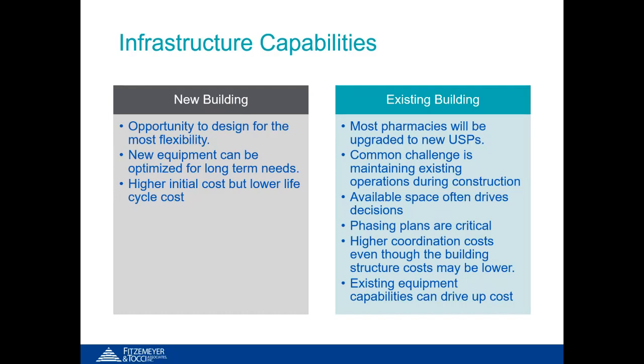Another major hurdle to existing pharmacy renovation is the capacity of the existing equipment. If the equipment was designed for use in a non-pharmacy space, the air handler, fans, and electrical infrastructure may not be able to convert to the higher required demand. Air handlers not designed for HEPA filters may be undersized for pharmacy applications due to the additional static pressure added by the filters themselves. In these situations, it is possible to include fan filter units to provide filtration and increase air changes to meet USP requirements.